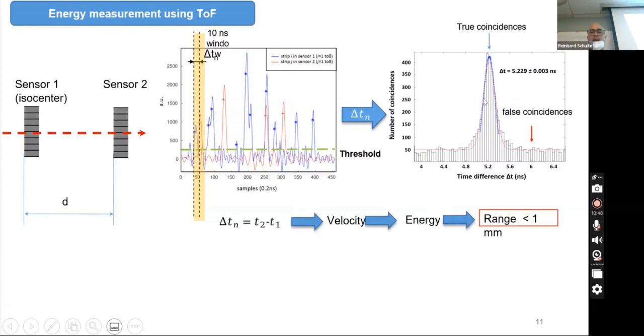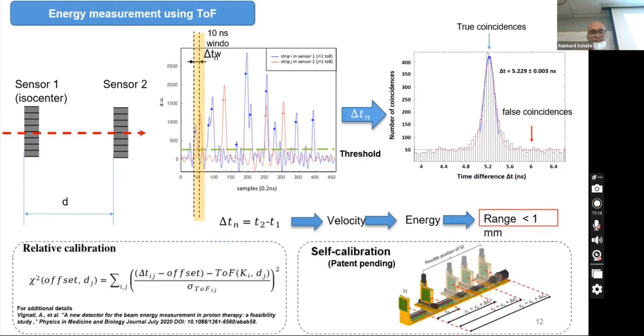Taking this distribution, the time taken by the proton to pass from the first sensor to the second sensor, so it's a coincidence, the same proton, and knowing the distance between these sensors, we can get the velocity, the energy, and therefore the range in water, which is the interesting parameter for the clinic. This approach is very sensitive to the picosecond level, so we need to calibrate our system in order to correct systematic errors like the offset due to the cable and also the distance between the sensors.